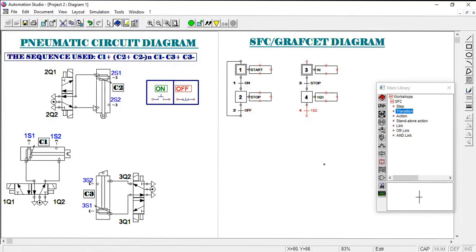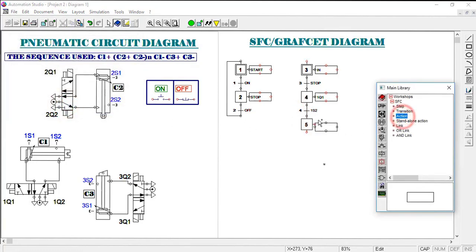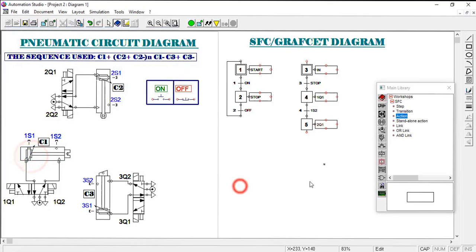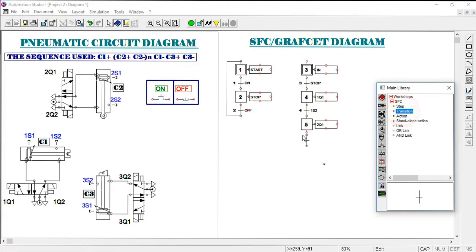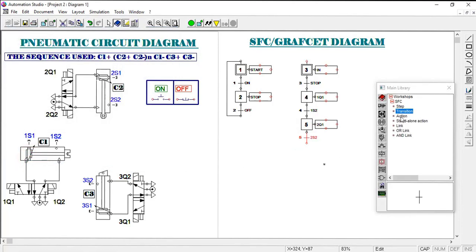When 1S2 is reached, it allows another solenoid to be energized. The next step — step five — has action 2Q1. When 2Q1 is energized, the valve changes position and forces piston two to slide along the cylinder for stamping. This is seen by sensor 2S2, which becomes the next transition.